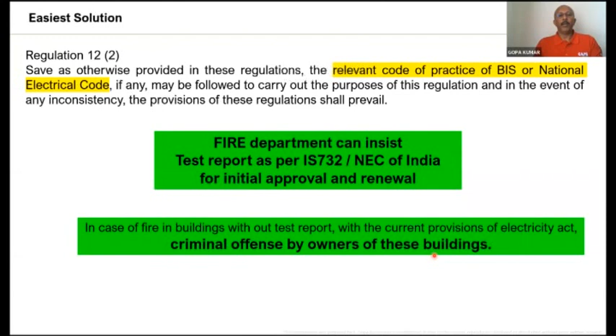Now, if this is not done, in case of a fire accident in a building, the current provisions of the rules and the act say that this is criminal negligence, and the owners of the building can face criminal offense charges. If you take up a few such cases, people will be afraid, or you can force people to follow the most modern safety practices. So one of the easiest ways to increase safety in our buildings is to do inspections as per NEC Part 1, Section 17, or IS 732. Do the testing as per this standard and rectify all defects. The fire department can ask for this test report in critical buildings, such as high-rise buildings and hospitals, for fire license renewal. If you do that, we can very much solve the problem of fire due to short circuit.